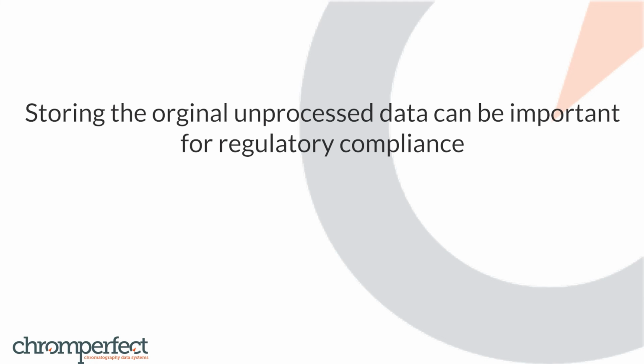Many of our customers work in highly regulated environments and must undergo regulatory audits. One of the key principles of data integrity is the rule that original data must be preserved. To address these problems, Chromperfect has separated these files and uses the extension RAW for raw files and BND for bound files. Raw files are untouched by processing and reflect the original data. Bound files reflect processed data.